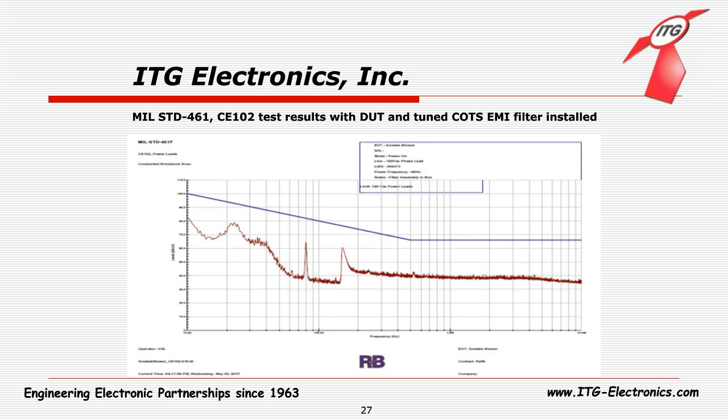Okay, thank you. As long as we're on the subject of safety, how does the maximum leakage current compare between military standards and, say, commercial standards? I know commercial standards, it's like 3 milliamps, isn't it? Right, it is. But in military, it's a bit higher. And I don't have the number in mind, but instead of 0.0001 microfarad, for example, you can use up to, depending on application, 0.01 or 0.02 microfarad to ground.